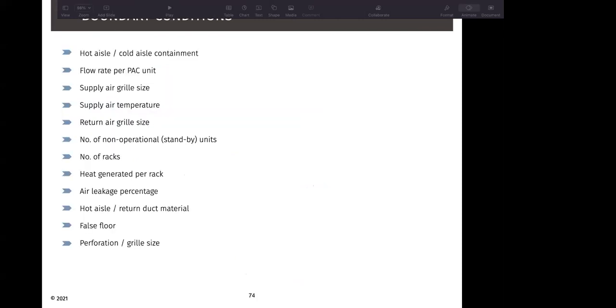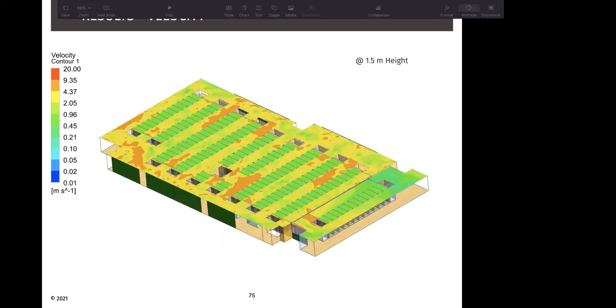The boundary conditions to be considered are hot aisle, cold aisle containment, flow rate per PAC unit, supply air grill size, temperature, return air grill size, non-operational standby units, number of server racks, heat generated per server rack, air leakage percentage, if any, the hot aisle return air duct material, if to be considered, and if there is any sort of false floor or perforation or grill size to be considered.